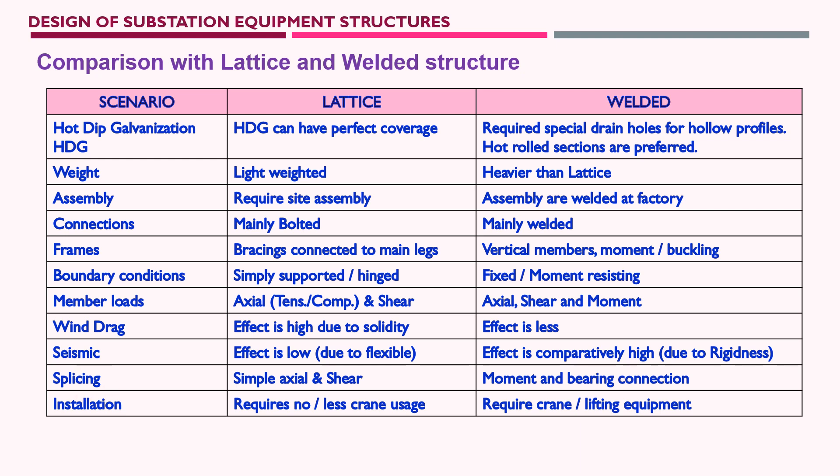For splicing connections in lattice structures, only simple axial and shear connections are required. In welded structures, moment and bearing connections are needed. Installation is easier for lattice because it requires less or no crane usage — structural parts are small and can be bolted at site. Welded structures require cranes or lifting equipment at site because the entire assembly is completed at the factory before galvanization, making lifting and placing on foundations more complex.